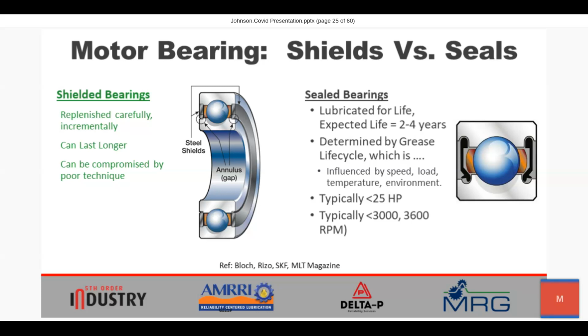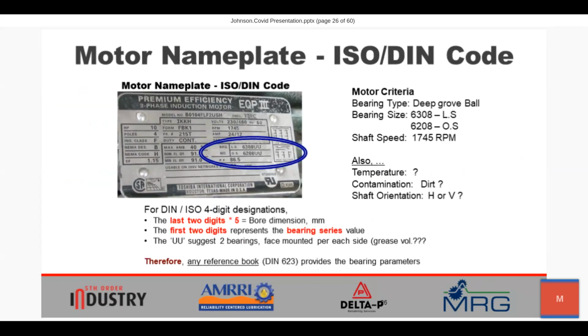They should have a 2 to 4 year service life, which is largely a function of the quality of grease used by the bearing manufacturer. We typically find these on smaller motors, smaller bearings, at lower shaft speeds. Where we see a shielded bearing, we need to know that we should proceed very carefully.